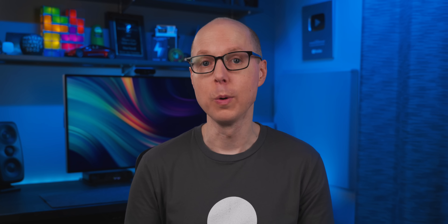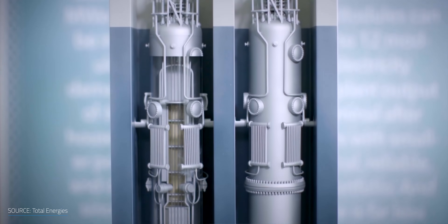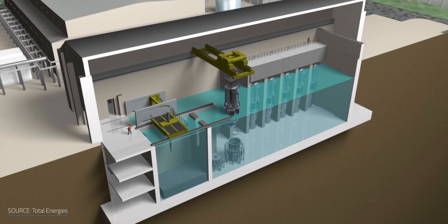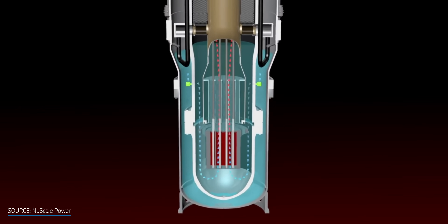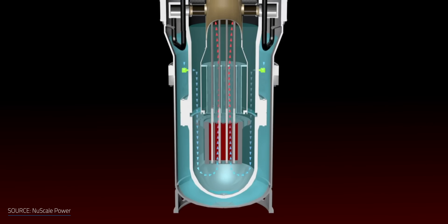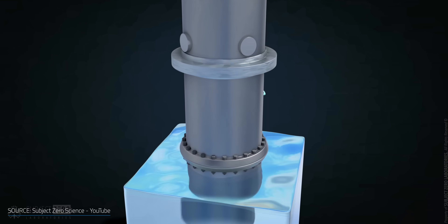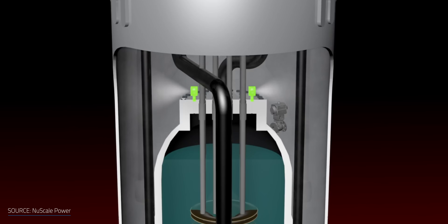When it comes to safety, SMRs include the latest safety features and security requirements. SMRs have smaller cores, which opens up space for the integration of more components into a single vessel, like the nuclear steam supply system. Their modular design results in simplified and safer systems, implying reduced severe failure modes, shielding requirements, and reduced off-site emergency planning zones. NuScale's SMR, for example, can passively cool itself utilizing natural water circulation without needing additional coolant or power supply, and its design is immersed in water to assist cooling during unusual conditions, not to mention specific valves that instantly release heat from the reactor vessel during an emergency.